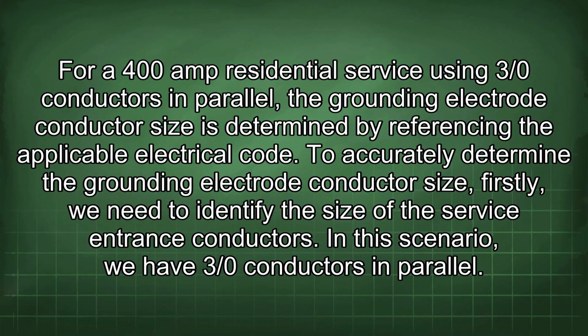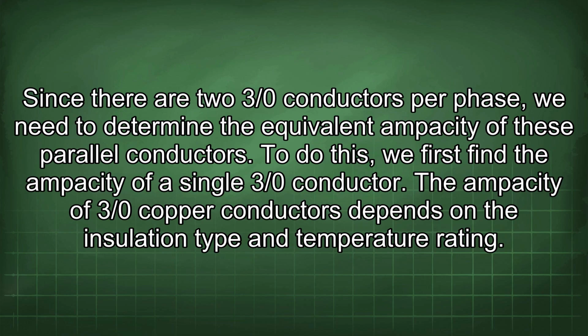For a 400 amp residential service using 3/0 conductors in parallel, the grounding electrode conductor size is determined by referencing the applicable electrical code. To accurately determine the grounding electrode conductor size, firstly, we need to identify the size of the service entrance conductors. In this scenario, we have 3/0 conductors in parallel. Since there are two 3/0 conductors per phase, we need to determine the equivalent ampacity of these parallel conductors.